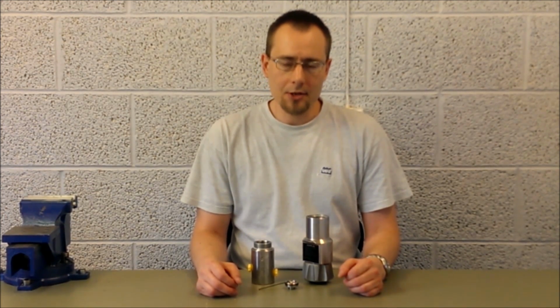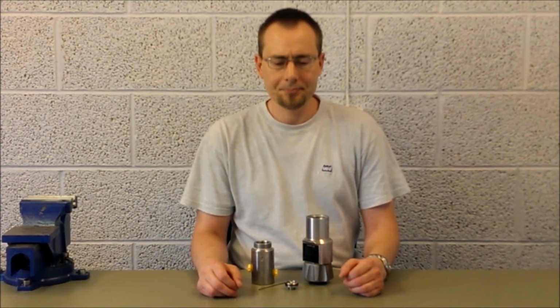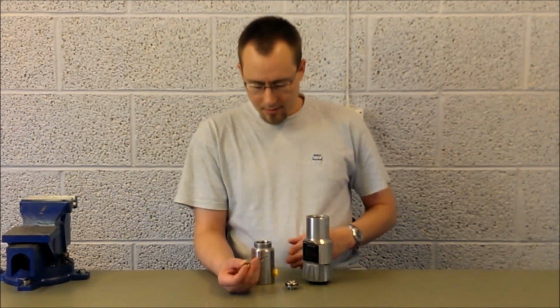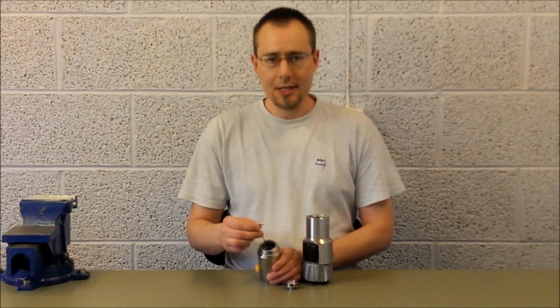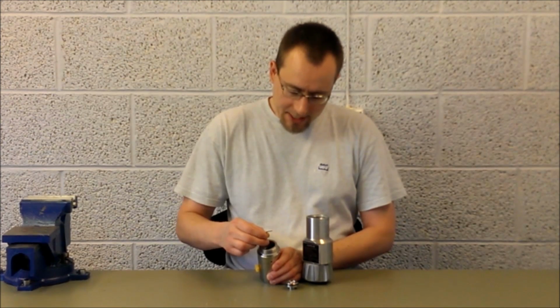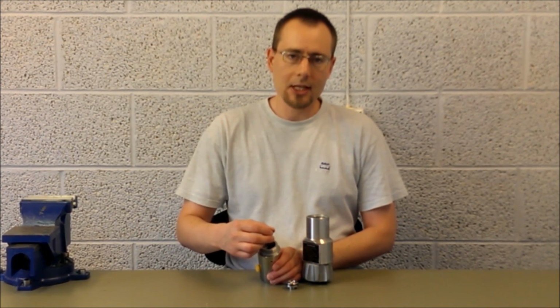Now we will demonstrate the adjustment of the dead band. The dead band is the difference between adjusted pressure and when the dump valve will open. For a 370 bar regulator, the dead band shall be approximately 25 bars. For a 690 bar regulator, the dead band shall be approximately 35 bars. For adjustment of the dead band, use a 1.5 millimeter hexagon key. Find the hole in the center of the pressure sensor. Make sure that the key is well fitted to the calibration screw.